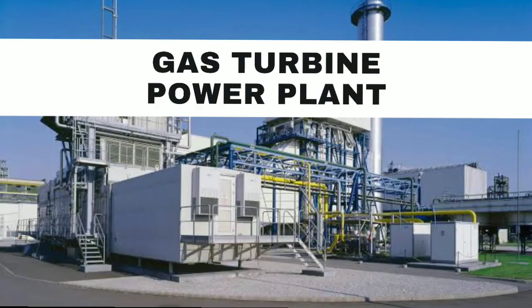Next, let's discuss about the gas turbine power plant. In gas turbine power plant, high pressure and temperature air is used to rotate the turbine, which in turn rotates the alternator to generate electrical energy. The working principle of a gas turbine power plant is same as that of a thermal power plant. In the case of a gas turbine power plant, compressed air is used instead of compressed steam to rotate the turbine. The air is compressed in a compressor. The compressed air is fed to the combustion chamber where continuous combustion of fuel oil is maintained. The hot gases so produced are made to run a gas turbine. In turbine, the compressed air is suddenly expanded. Hence, it gains kinetic energy, and because of this kinetic energy, the air can do mechanical work for rotating the machine.